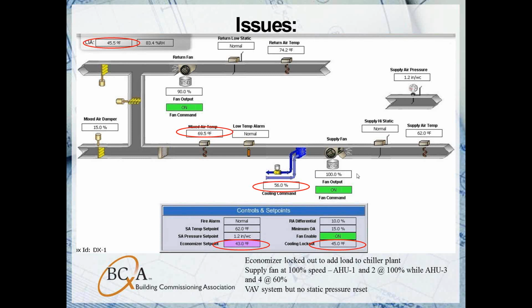If you look at the other air handlers that are headered together with this unit, you'll see that air handlers 1 and 2 typically operate at 100%, while 3 and 4 are operating at a lower speed, typically 60%. So there is some fighting going on there. Fans 1 and 2 are operating faster than they should, while 3 and 4 are operating slower than they should. Like I said, this is a VAV system, but we don't have static pressure reset programmed in the system here, so they're missing out on an opportunity there.